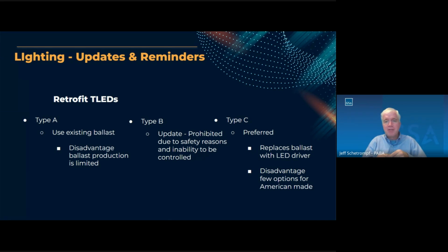Then we have type B. So these bypass the existing ballast and are direct wired to the mains. That means if you're not paying attention, the simple act of replacing the bulb in a live fixture exposes you to voltage levels. So new in the 24 P100, we no longer allow type B retrofits in our buildings. Then finally, we have type C. So these are going to save you the most energy. They're going to eliminate the ballast, but they also cost more. So type C is the preferred method because we all know that at some point down the road, we're eventually going to have to rework those type A's as the ballast lines get discontinued.